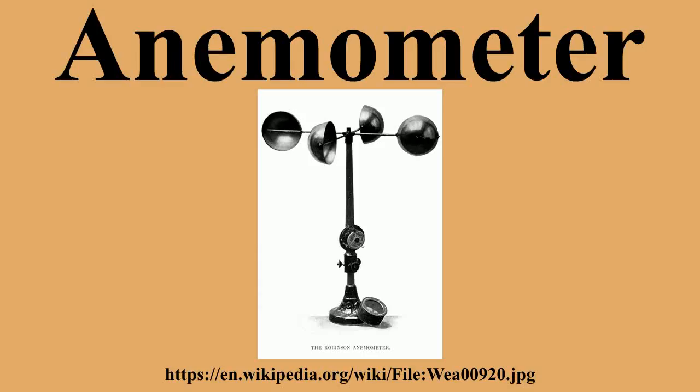It might appear at first sight as though one connection would serve, but the differences in pressure on which these instruments depend are so minute that the pressure of the air in the room where the recording part is placed has to be considered. Thus, if the instrument depends on the pressure suction effect alone, and this pressure suction is measured against the air pressure in an ordinary room, in which the doors and windows are carefully closed and a newspaper is then burnt up the chimney, an effect may be produced equal to a wind of 10 miles per hour, and the opening of a window in rough weather, or the opening of a door, may entirely alter the registration.